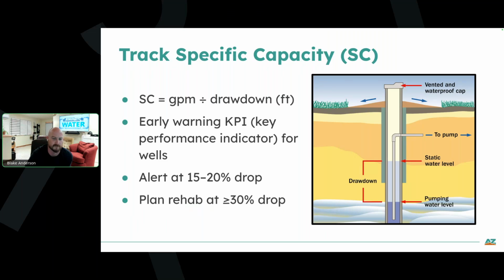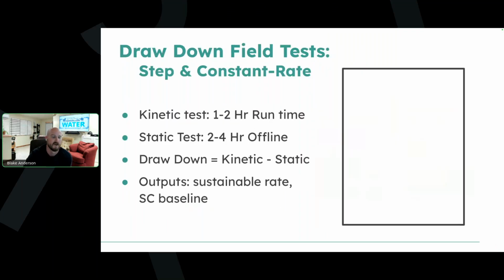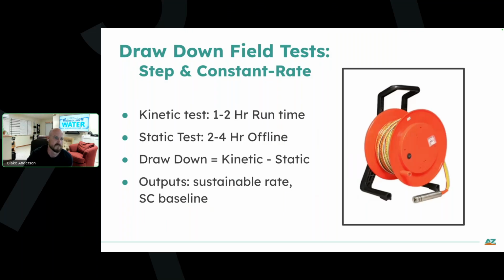And so to do that, like I said, you'll be needing to measure your static levels, your pumping levels, and what your drawdown is on a relatively regular basis. You want to use the same measuring point, same method when you do it. And ideally, you're doing it pretty regularly because you want to be able to know seasonal impacts, demand changes, and compare year over year.